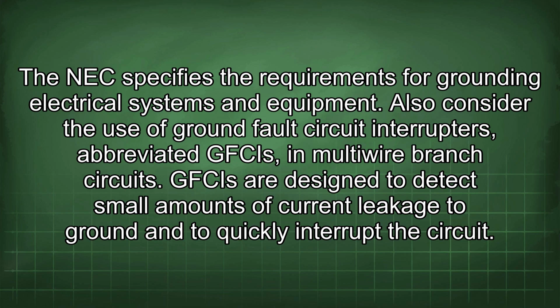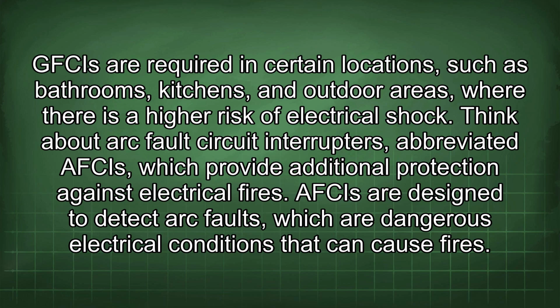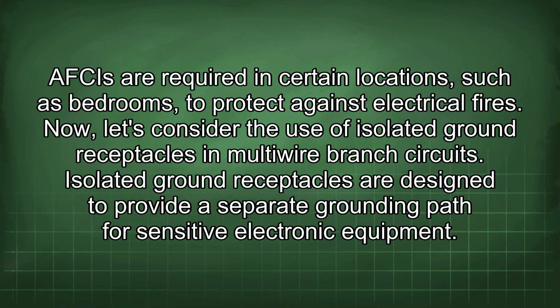Also consider the use of ground fault circuit interrupters, abbreviated GFCIs, in multi-wire branch circuits. GFCIs are designed to detect small amounts of current leakage to ground and to quickly interrupt the circuit. GFCIs are required in certain locations, such as bathrooms, kitchens, and outdoor areas, where there is a higher risk of electrical shock. Think about arc fault circuit interrupters, abbreviated as AFCIs, which provide additional protection against electrical fires. AFCIs are designed to detect arc faults, which are dangerous electrical conditions that could cause fires. AFCIs are required in certain locations, such as bedrooms, to protect against electrical fires.